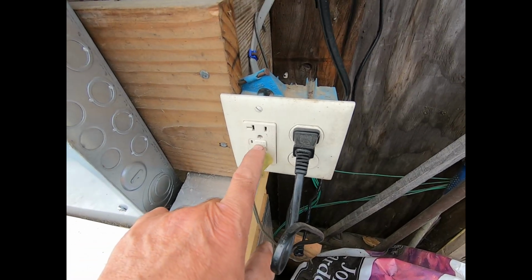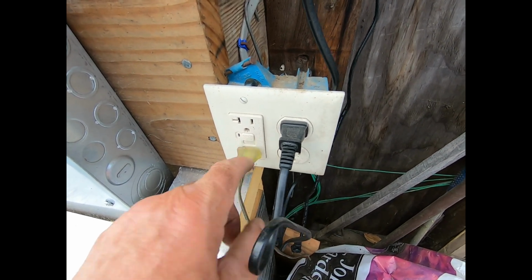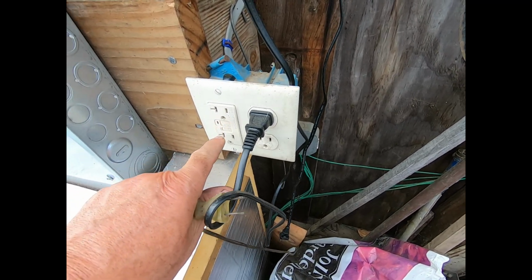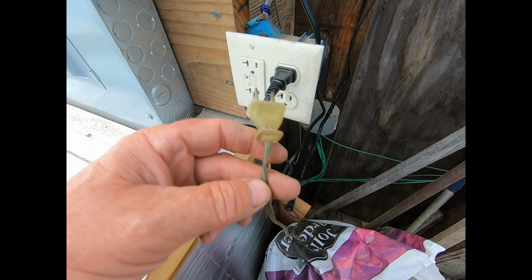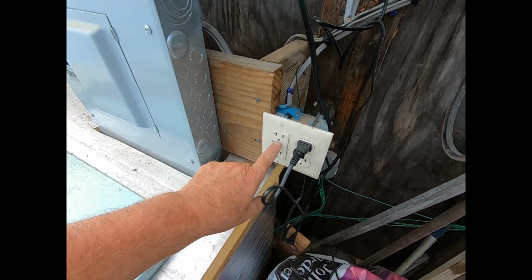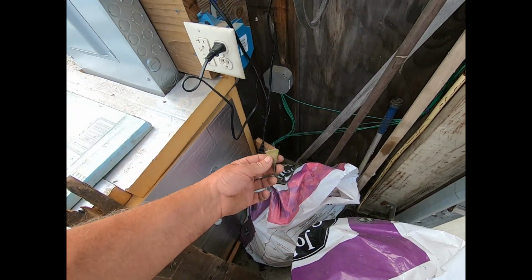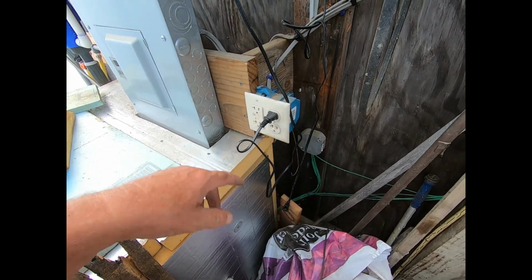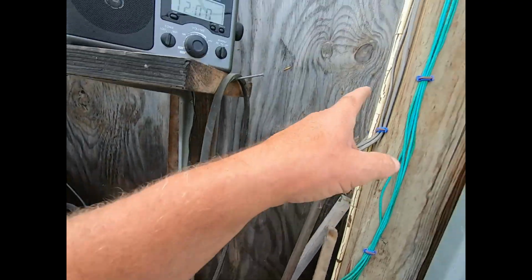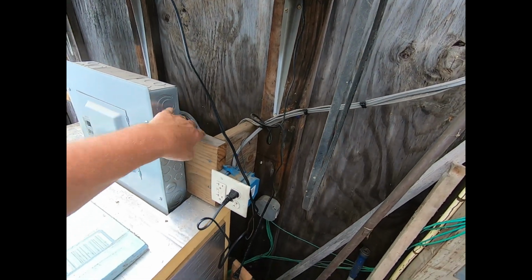Look at this, guys. What do you bet that's the problem? Where's the problem at? Yeah, it's in that light right there. At O'Reilly Auto Parts. That's O'Reilly Auto Parts. Yeah. So that light is in there setting on the damp ground. Obvious, it tripped the ground fault. So, simple. I never even thought to look at that. I really wasn't sure if that actually went down and went through here, if it went right direct into here, but it's obvious.